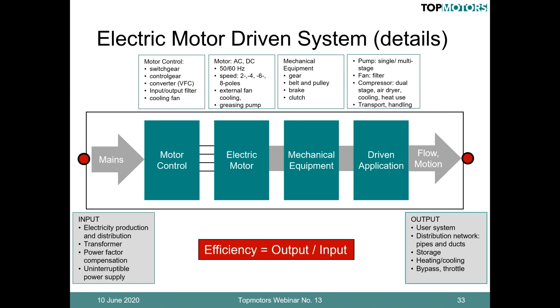I remind you of the second slide I showed at the very beginning. And then the mechanical equipment can be a gear, a belt and pulley, a brake and clutch. If you don't have any of that, you're well off and you're more efficient. But for many applications, it's still typical to run the motor for a fan over a belt and a pulley, even if that's an extra machine and extra cost and extra losses. And on the right side, on the driven application, we have pumps, but pumps can be single or multi-stage. You have fans. Fans have a filter. You have a compressor that can also be a single or dual stage, has an air dryer, has a cooling system, eventually has a heat use, and you have all the transport and handling system.